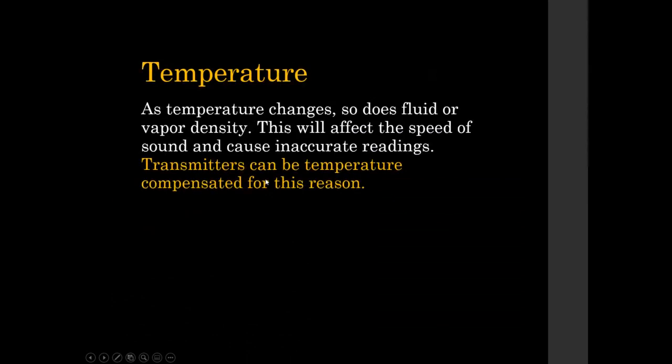Temperature, as mentioned earlier, as it changes, so does the fluid or vapor density. This has an effect on the speed of sound and can cause inaccurate readings. To get around this, most transmitters are built with temperature compensation built into them already, so it's not typically something that we as technicians have to deal with.